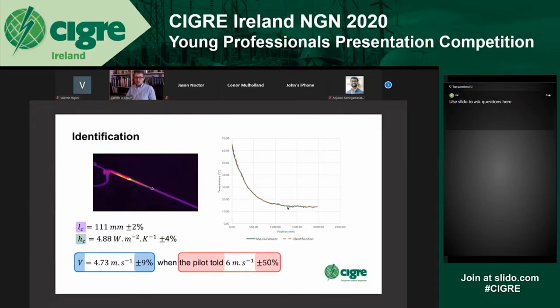If we compare it to what people are usually doing, they're asking the pilot. In this specific case, the pilot said 6 meters per second, getting the information from the weather station at the closest airport, not really close to this specific joint we're looking at. We estimate the uncertainty at about 50%, but it could be way worse, especially because the pilot doesn't give you the direction of the wind, whether it's parallel or perpendicular to the conductor. That has a huge impact on the way it's cooling down the conductor.